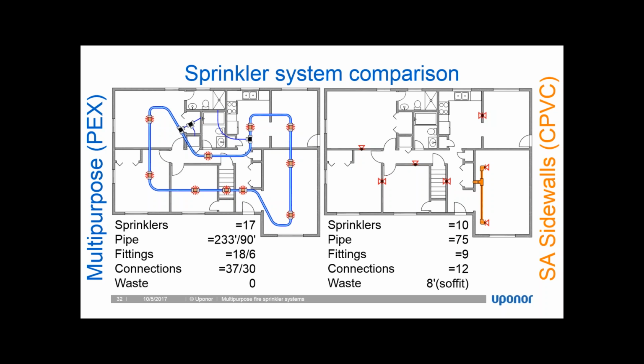But because of the location of the very lowest sprinkler in this upper level, it's on a cold wall, and I wouldn't necessarily want to install that pipe inside the cold wall. So I would pop the pipe out and build a soffit around it. So I included the soffit in the waste category because it's really not necessary when you're using a multi-purpose system to worry about cold walls or things like that. We have a bunch of guidelines regarding Uponor PEX tubing installed in attic configurations. I would say that you don't have to worry about how that's installed as long as you follow the Uponor guidelines for that. So there is a wasted soffit, I want to say, in the waste category for sidewall applications.